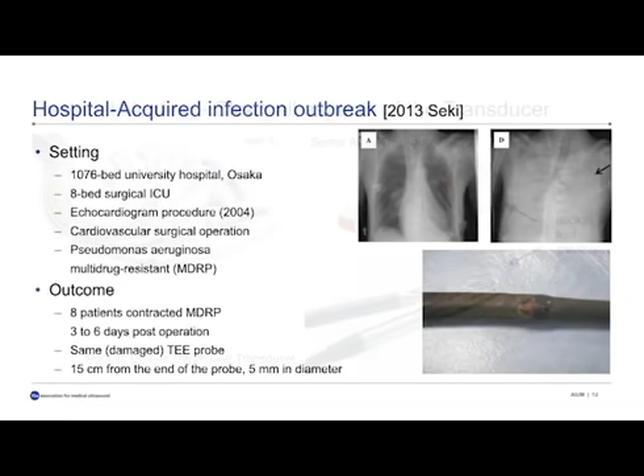And 15 centimeters from the end of the probe, there was a 5-millimeter diameter defect. And this defect is where cultures could grow. And even high-level disinfection would not be able to remove these cultures because it wasn't mechanically cleaned to begin with. And they did not use a sheath. And so it's really important to clean the ultrasound transducers, not by just procedural high-level disinfection, but by really understanding what the cleaning entails.